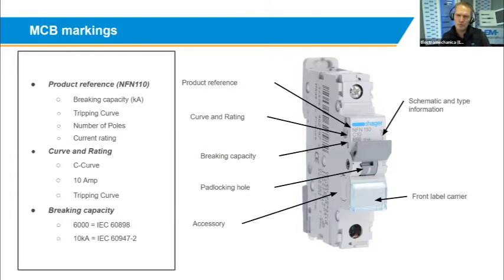And then what's important for the South African market is the 10 kA written on the product. That's done according to the IEC 60947-2 standard, which is more applicable to South Africa, and internationally that is seen as the industrial standard. For South Africa, we also need to comply with compulsory certification, which is VC 8036 for circuit breakers, and that refers back to the IEC 60947-2 with a few amendments. But I'll show you later on that we do comply with all these specific standards and requirements for the South African market.